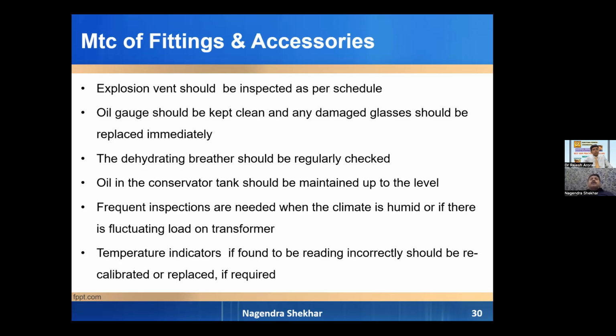Explosion vent should be inspected as per schedule. Oil gauge should be kept clean. If glasses are broken, we have to replace them immediately. Dehydrating breather, as I told, we have to check them, and so on. So we are running out of time. I'm skipping this slide also.